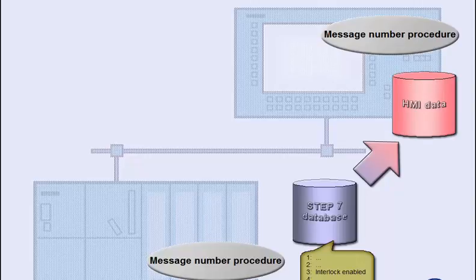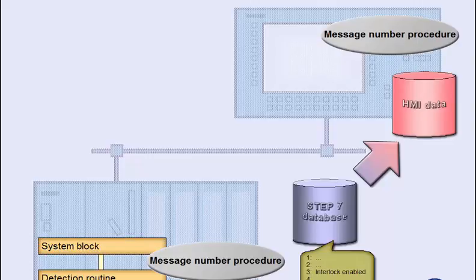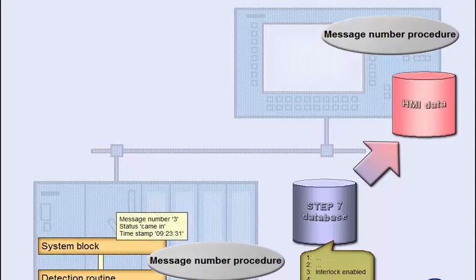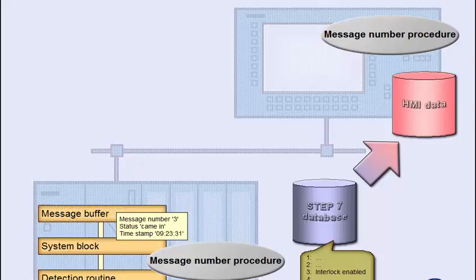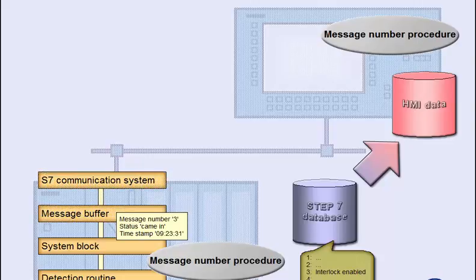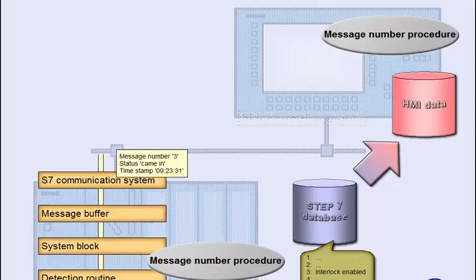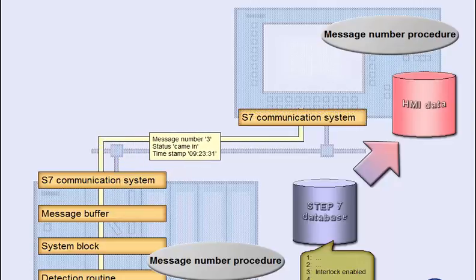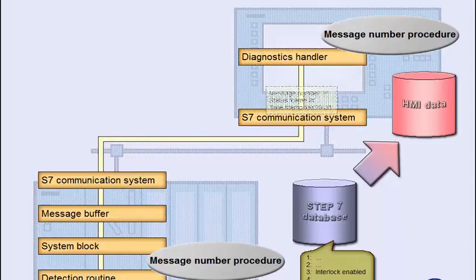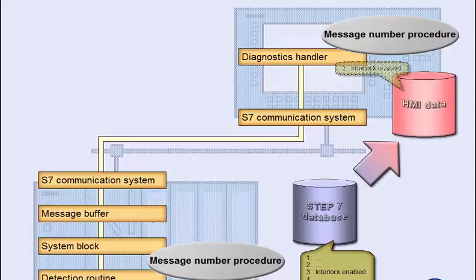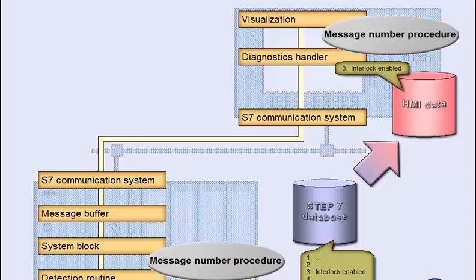At runtime, a system internal or user-programmed detection routine detects the event to be reported, and calls a special system block to organize the message. The system block transfers the specific information, such as message number, status, and timestamp, into the controller's message buffer. The S7 communication system now generates a message telegram and sends it to the operating device. Here, the internal diagnostics handler adds the texts that correspond to the message number and displays the message.